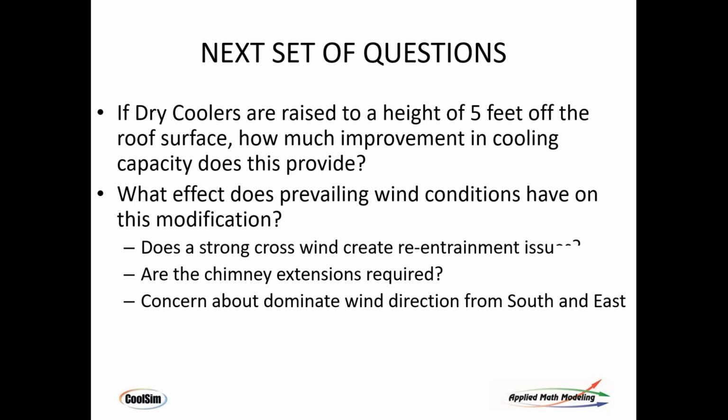So one of the things we thought here is, well, what if we jack them up? What if we get them up to 5 feet, put 5 feet underneath them? Will it improve the cooling? And if so, how much? This is exactly what you can do with CFD. It allows you to play these what if games. What if we jack it up? How does it affect it under the same assumptions? Very hard to do in the real world, by the way. It's hard to hold parameters constant. Nothing stays constant in the real world, but here you're able to do that.